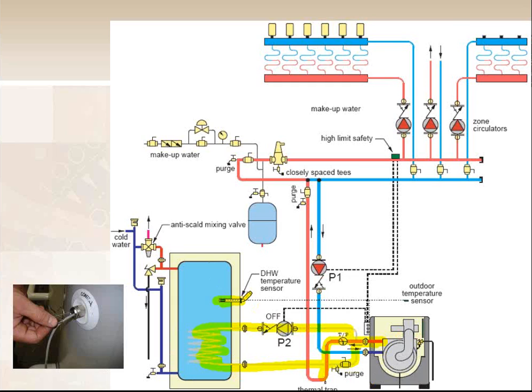Once that sensor says, hey, I'm happy, I'm satisfied, he sends a signal back to the boiler, says, I'm all good, thank you very much for the hot water, and now I can turn pump number 1 back on and start heating my building. If I stop heating your radiant floors for 10 minutes to heat your domestic tank, no one's going to know. I mean, you can stop heating for 2 hours and no one's going to know. There's so much mass in the radiant floor. But even baseboard and radiators and stuff, if I stop using them for 10 minutes, they'll still be hot and people will still be getting heat that's residual while I heat your domestic tank up. So it's a fantastic way to save some energy here.